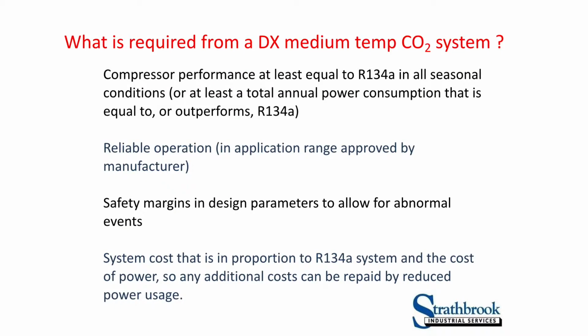So we came up with an idea of cooling the refrigerant coming out of the gas cooler with a secondary system in hot weather, and that secondary system's turned off for most of the year. That allowed us to run the system as a subcritical system all year round. But there are some complications because we're talking about much higher pressure.